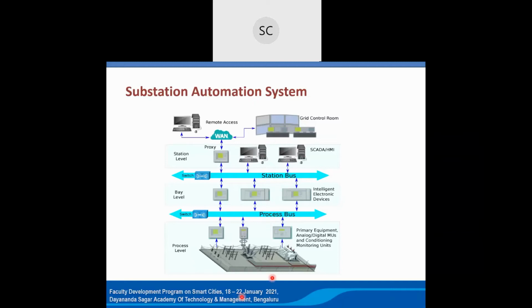So in these modern substations, when we implement numerical relays for distribution automation purposes within the substation automation system, we call it a process bus. In the process bus, whatever primary equipment details - that is voltage and currents - comes through CT/PT to the process bus. Nowadays the process bus is also getting digitalized, using what we call merging units, along with optical CT/PTs. Optical CT/PT outputs will directly be in samples, so we can connect directly to the merging unit. Or if the merging unit is not there, it comes through conventional CT/PTs that go to the numerical relays as an input.